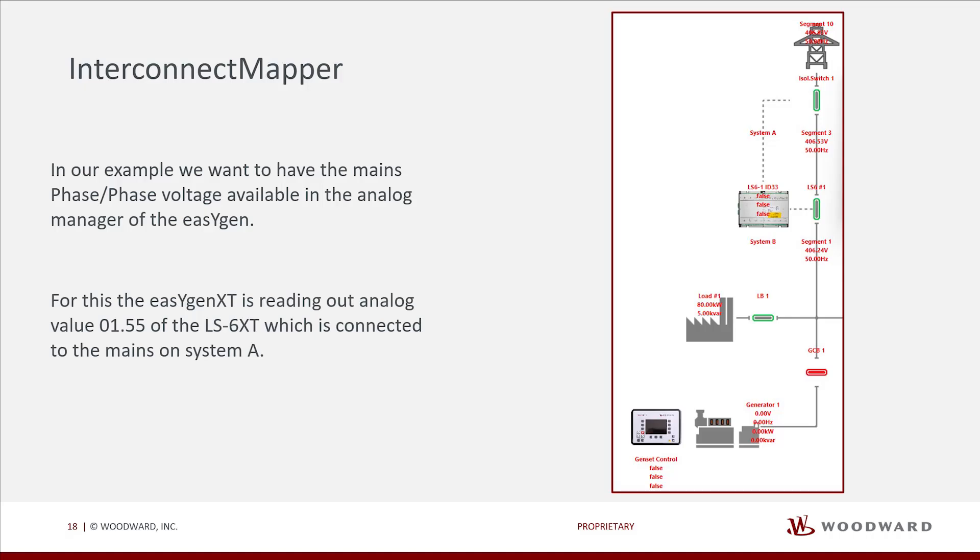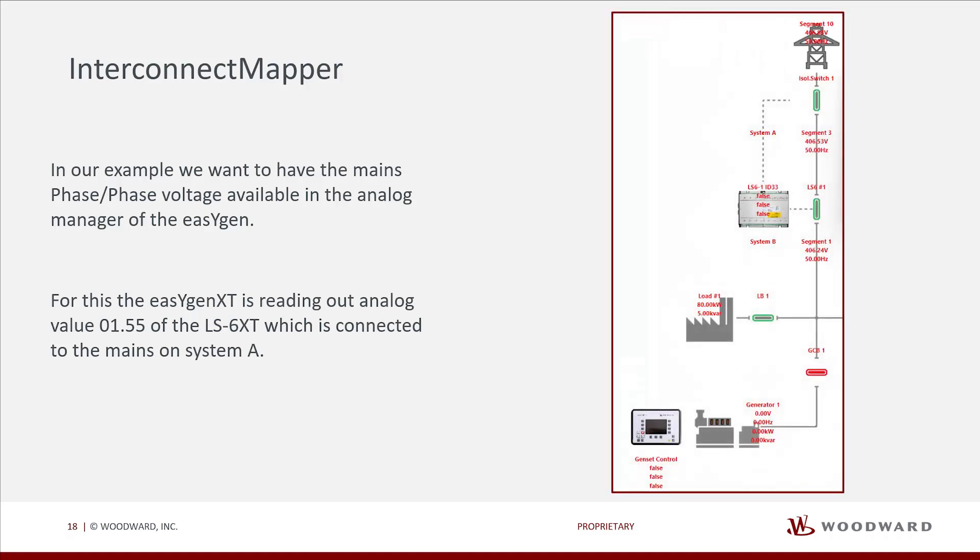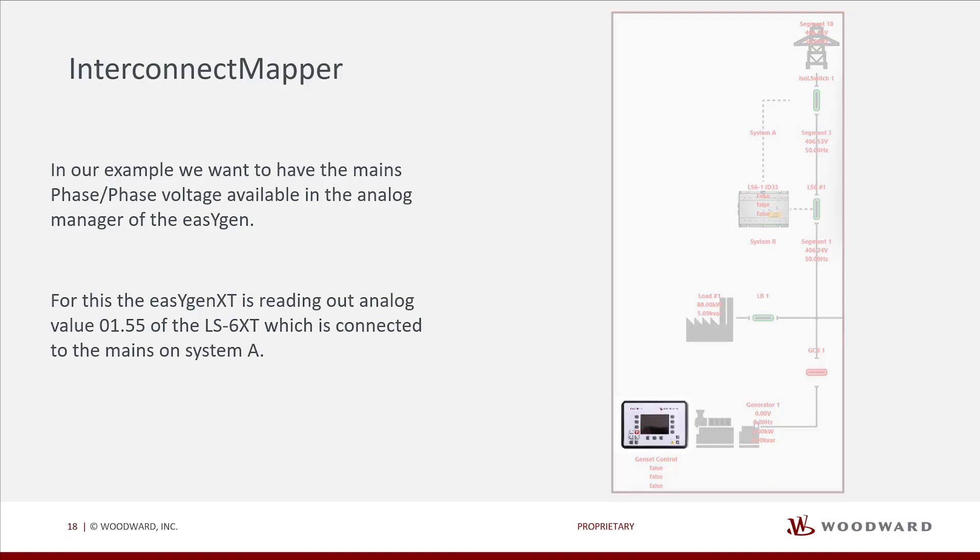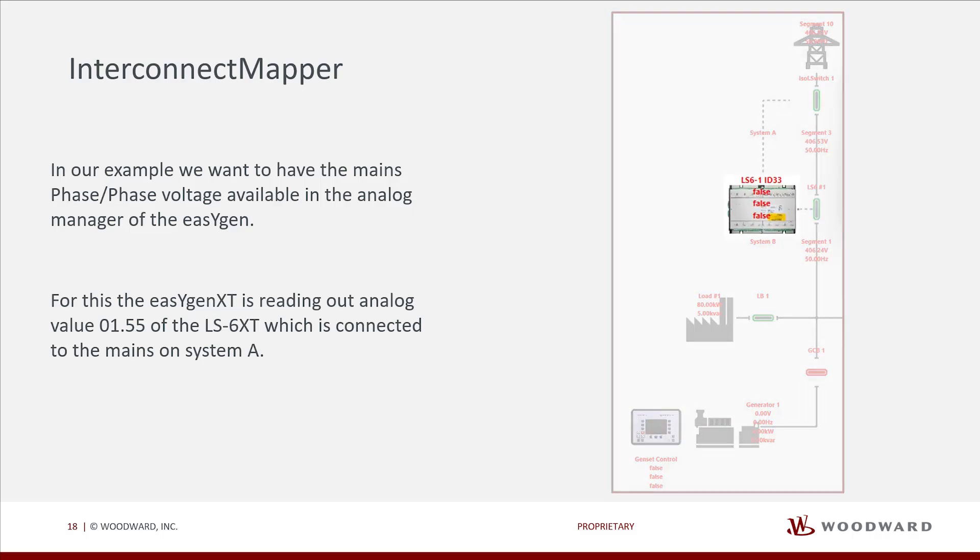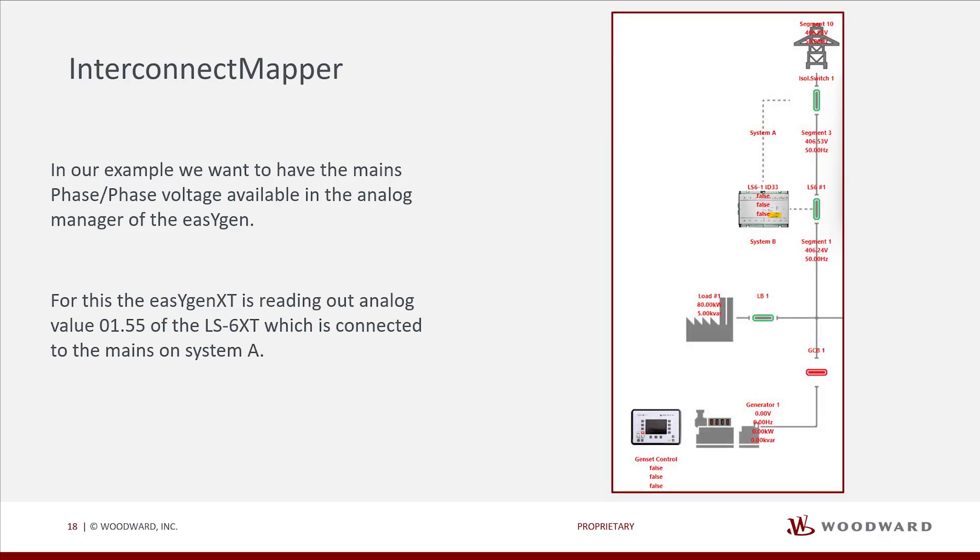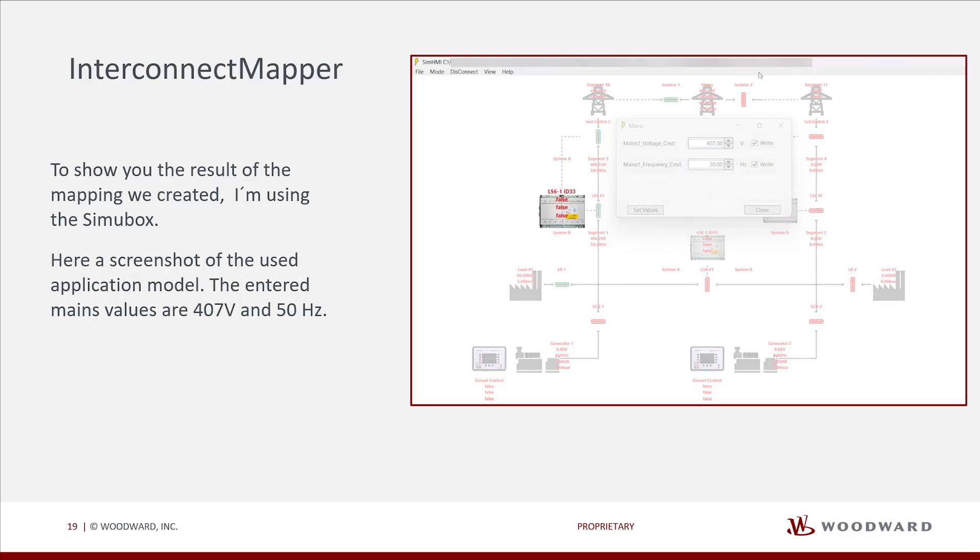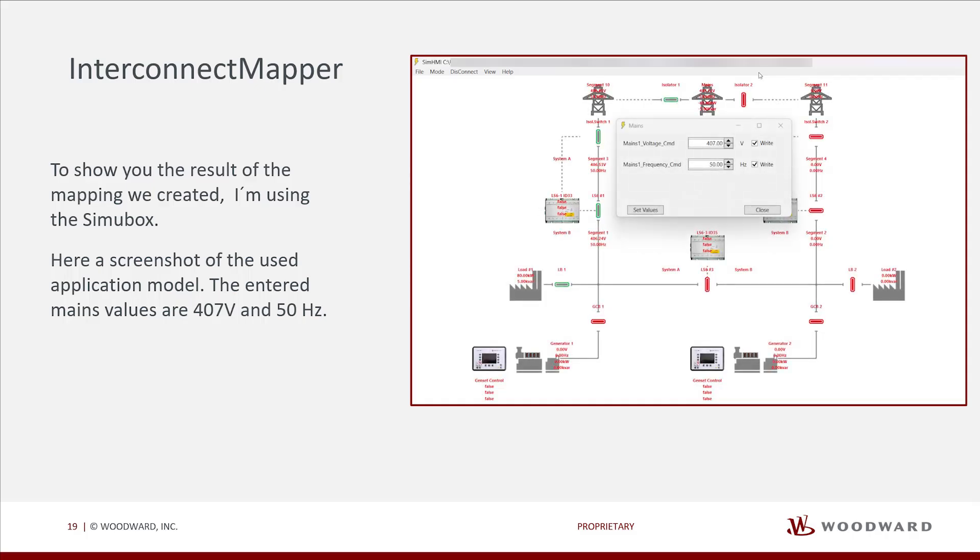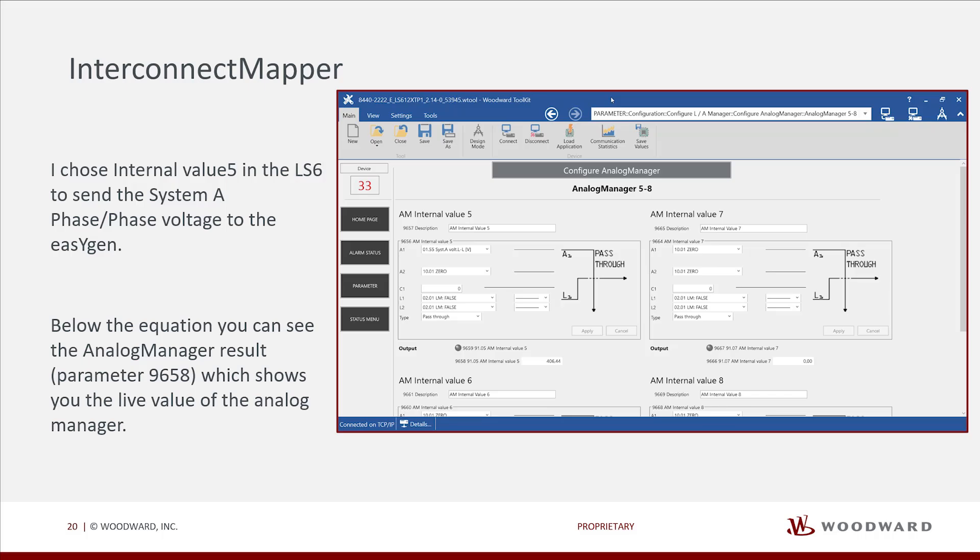In our example, we want to have the mains phase slash phase voltage available in the analog manager of the EasyGen. For this, the EasyGen XT is reading out analog value 01.55 of the LS6 XT, which is connected to the mains on system A. To show you the result of the mapping we created, I'm using the SimuBox. Here, a screenshot of the used application model. The entered mains values are 407 volts and 50 hertz. We will work with LS6 ID33 and EasyGen of generator 1. I chose internal value 5 in the LS6 to send the system A phase slash phase voltage to the EasyGen.